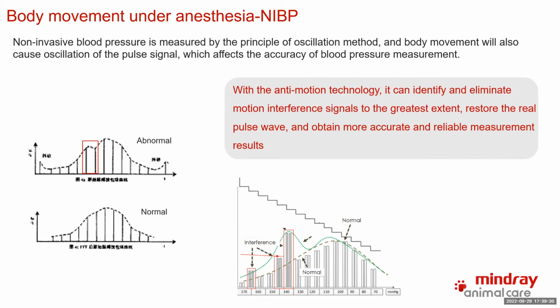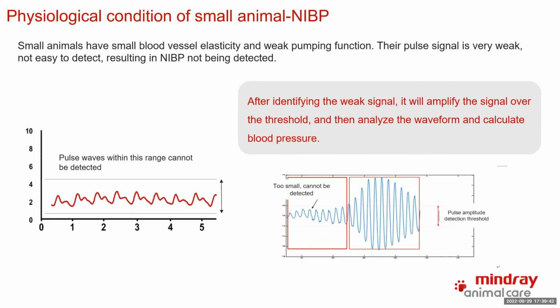So even if the patient under anesthesia has some movement, when we measure the NIBP, we can still remove that interference and get an accurate result for the NIBP. So that's for the body movement. And also for the NIBP, sometimes for some small animals, they have small blood vessel elasticity and weak pumping function. So their pulse signals are very weak, and it's not easy to detect their pulse signals, and we cannot get the result.